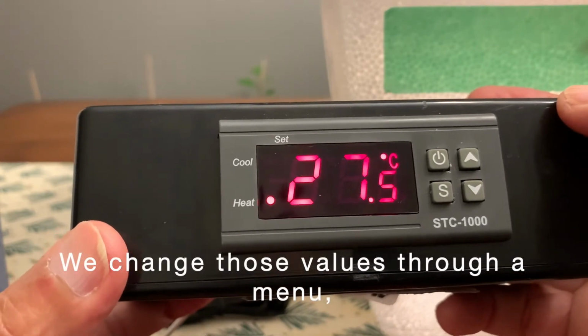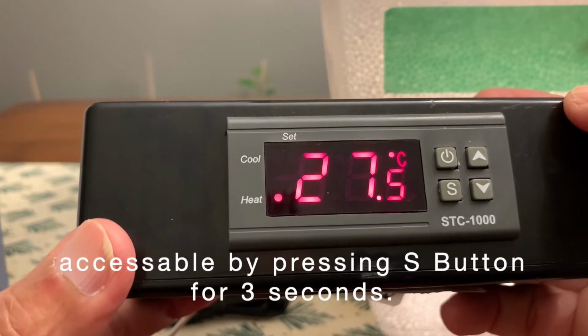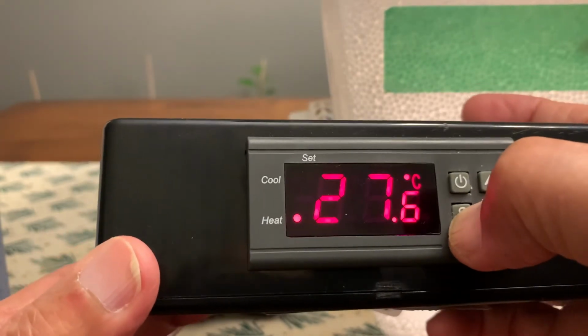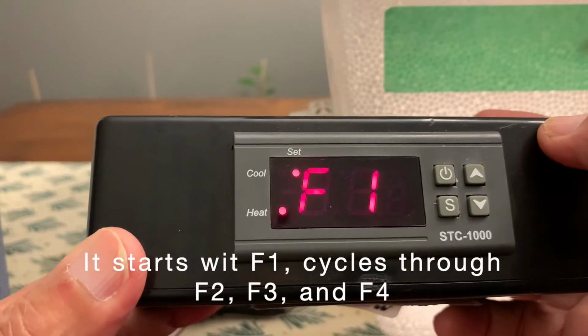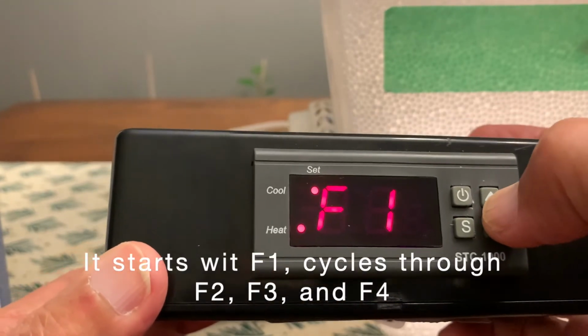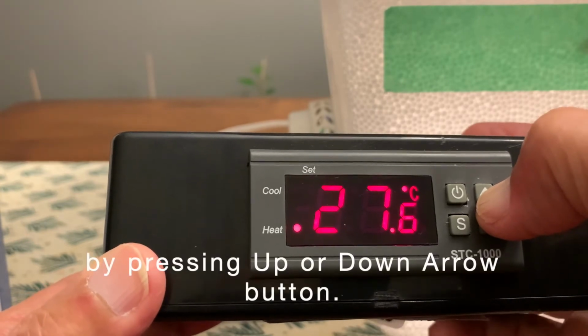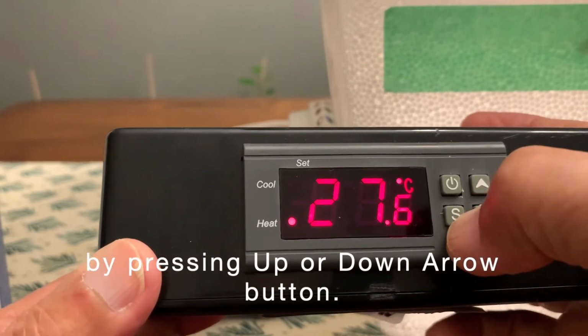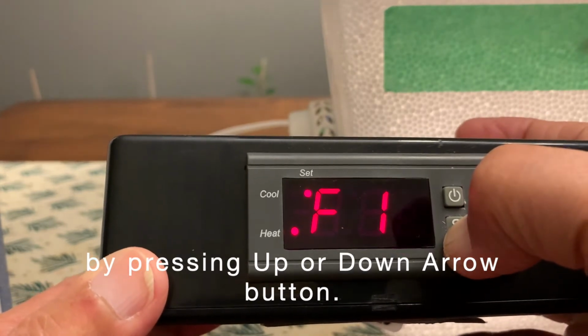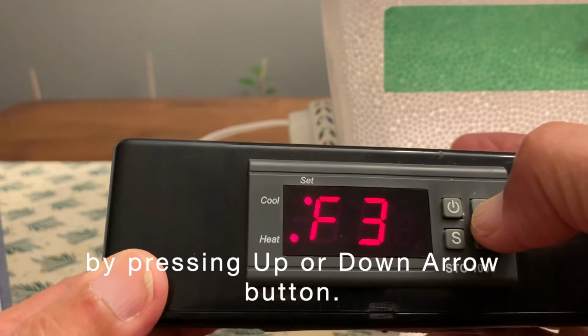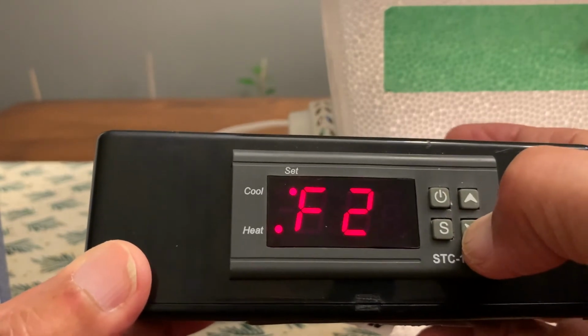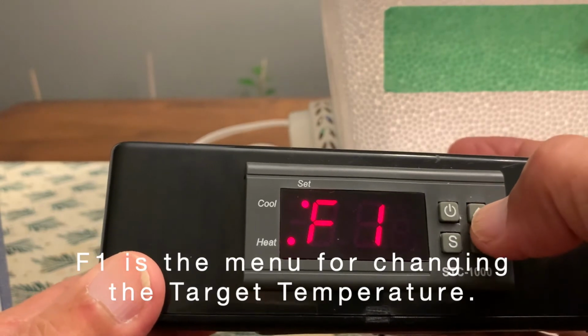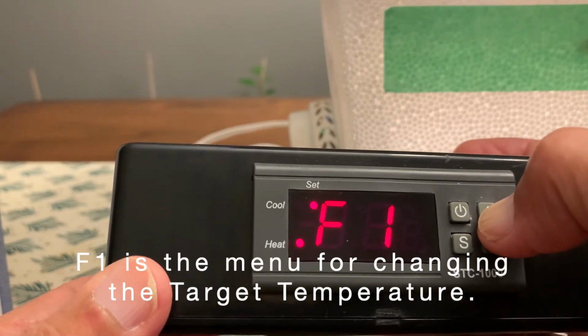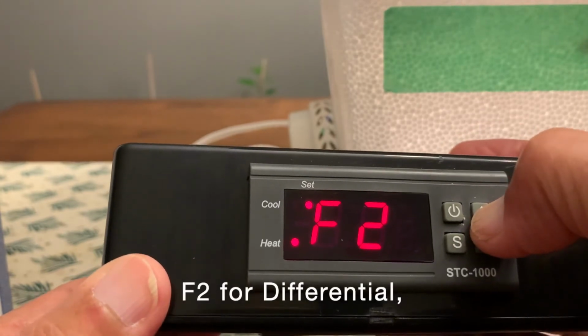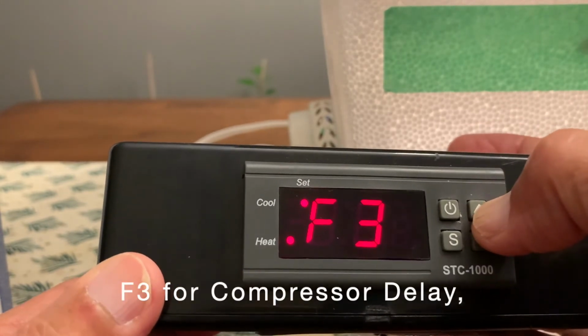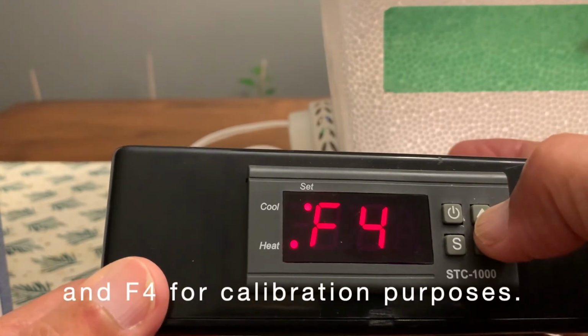We change these values through a menu accessible by pressing S button for 3 seconds. It starts with F1, cycles through F2, F3, and F4 by pressing up or down arrow button. F1 is the menu for changing the target temperature. F2 for differentials. F3 for compressor delay, and F4 for calibration purposes.